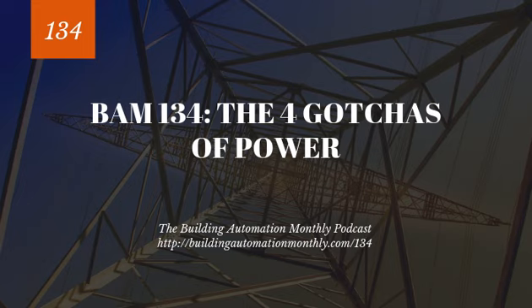You need to understand that, because you can power up your loop, get all your actuators wired up, everything's great. You start actually driving the actuators and stuff starts shutting off. That's because your operated VA load is higher than your idle load, your amp draw load. So that is important for you to understand, the difference between idle and operated load. That's something I didn't know for quite a long time.